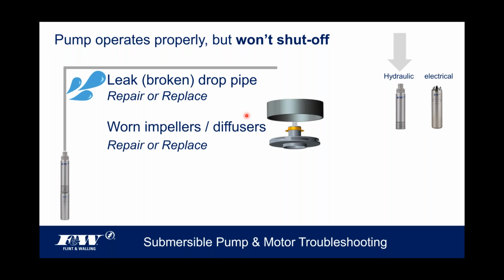Another reason why a pump might not shut off, and I talked about this just a few seconds ago, is that it's far enough along in its life cycle. Things are wearing out and the performance is dropping. When we think of things wearing out inside the pump end, the wet end, you've got to look at what we call our impellers and our diffusers. I've got an image of what those look like. In a submersible pump, you'll have several of these stacked one on top of another. A half-horse 10-gallon-a-minute submersible pump probably has 8 of these in there. A 1-horse 19 might have 5 or 6. Nonetheless, there's going to be a series of impellers and diffusers inside that pump that, if they're not just flat worn out, could be clogged up. And again, we're looking at either repair or replace.